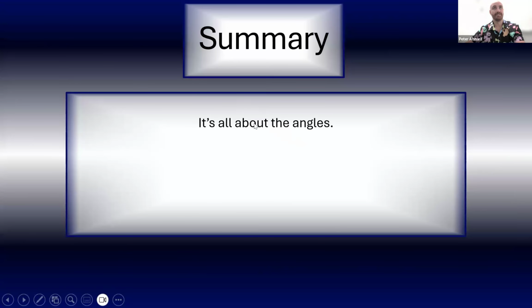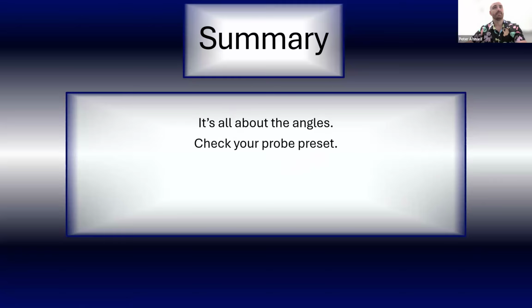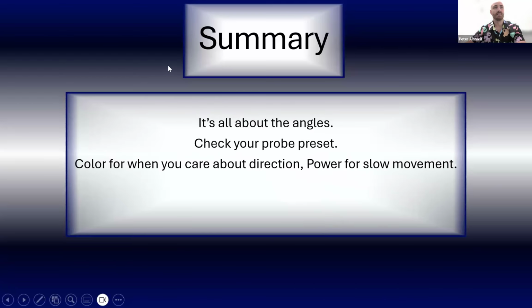So just a little summary here. It's all about the angles. The biggest problem that happens is that the angle of your pulse wave Doppler, the probe, is perpendicular to the flow. Just by adjusting the angle, you address many of the issues with Doppler. Check what your probe preset is. You don't really need to go into the machine settings necessarily. Just by having an appropriate preset for what you're imaging also addresses a lot of issues.